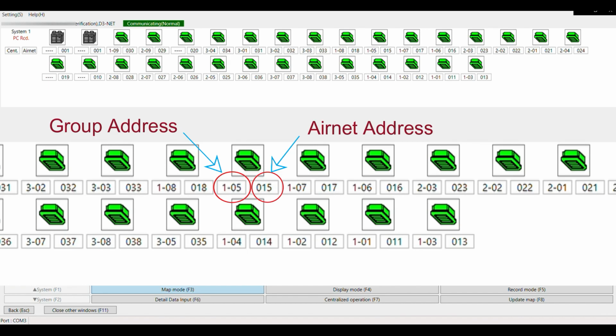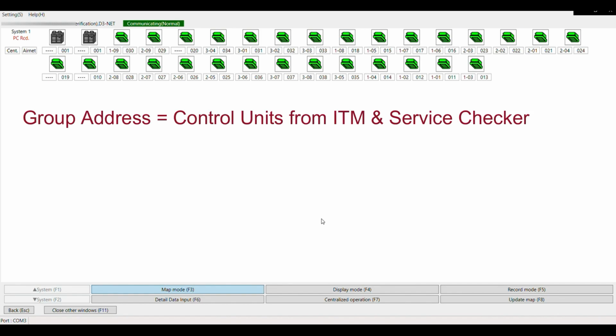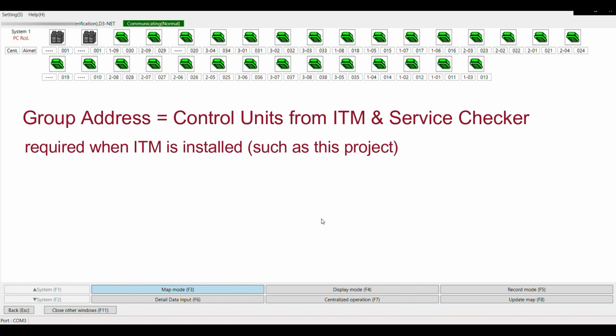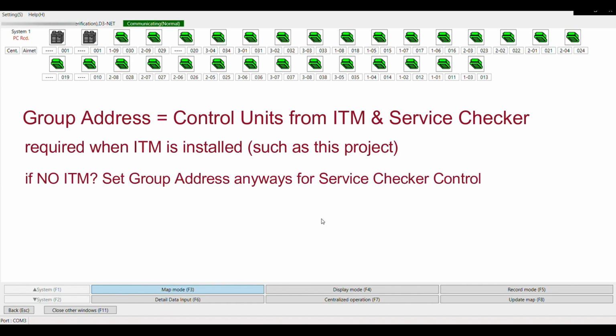I always recommend programming both of these items. For starters, you're already in the settings of the thermostat programming field settings, and this takes literally a couple of extra seconds to program if you have your as-built with you. Programming the group address allows you to control the indoor units from the ITM and or from the service checker tool. And since we have an ITM central controller on this project, the group addresses were going to be required to be controlled from the ITM anyways. Many times techs will ask, do I need to program this if I don't have an ITM? And I always say yes, because at some point you'll want this control available from a service checker when taking runtime, especially in some cases where you don't have access to all the spaces and there's no ITM on site.